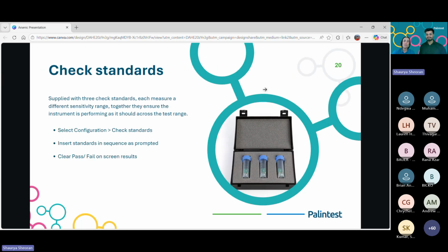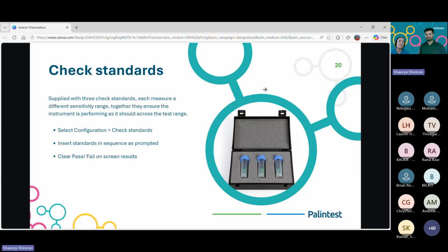So, check standards again, just to cover this, this is what they look like inside the kit. There are 3 check standards supplied, all covering a different sensitivity range. We've only covered arsenic today, but the Kemio is capable of covering many parameters across many concentration ranges. These 3 check standards together ensure that the instrument is performing as it should across all of those. It's really simple to do.